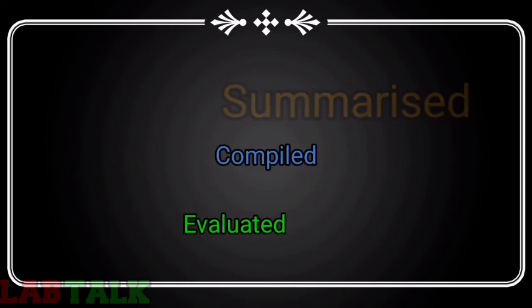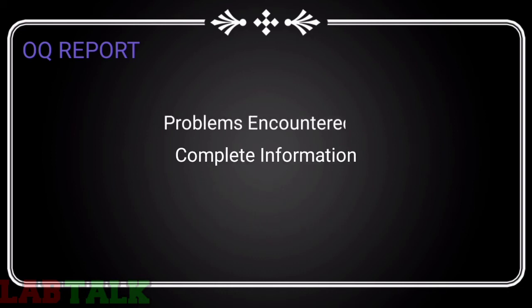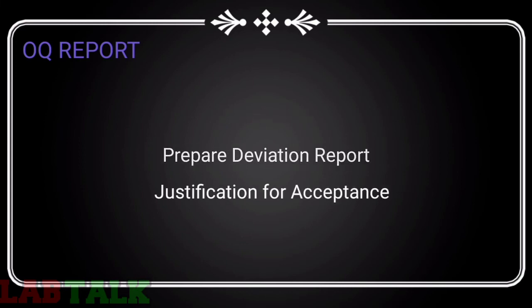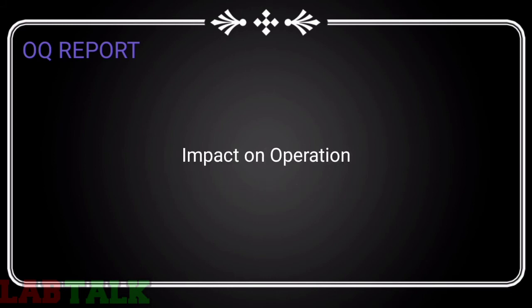After completion of OQ, the results are summarized, evaluated, and compiled in an OQ report. The report should include: date study initiated, date completed, observations made, problems encountered, completeness of information collected, summary of deviation reports, results of controls and alarm tests, sample data if appropriate, location of original data, other relevant information, and conclusions on the validity of the equipment and system operations. Prepare a deviation report including justification of acceptance and impact on the operation; all deviations and measures taken to eliminate them should be documented.